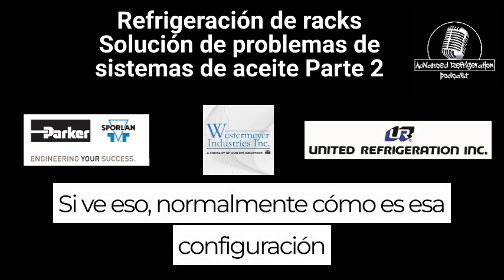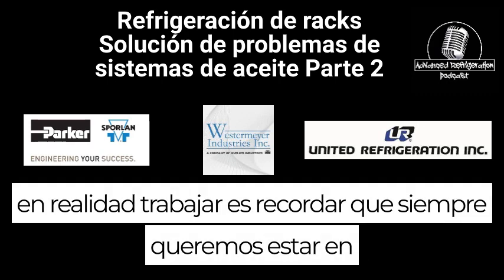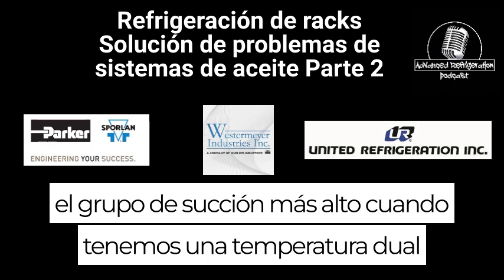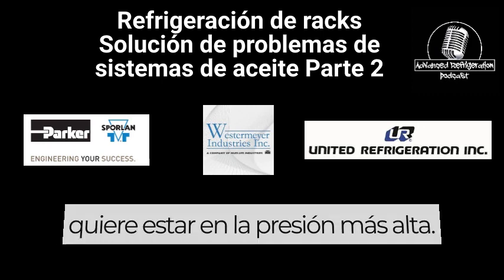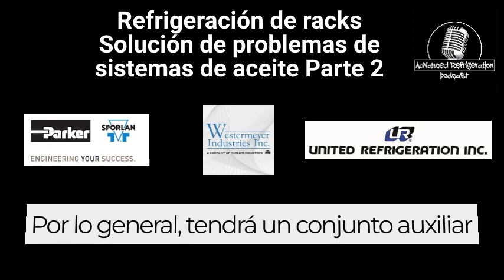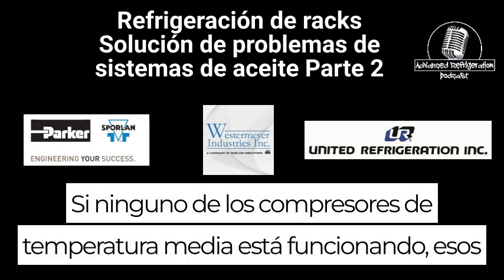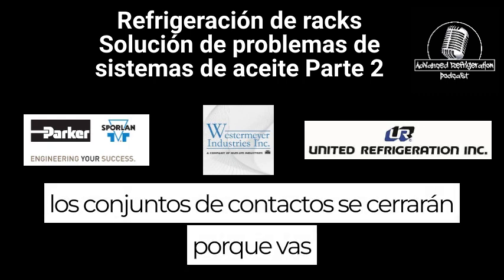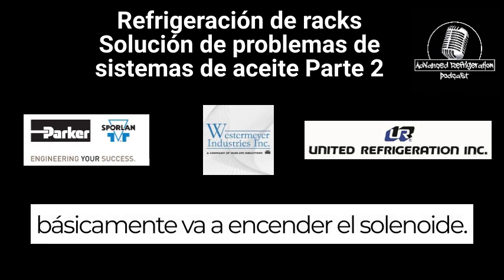If you do see that, typically how that setup is working is, remember, we always want to be at the highest suction group when we have a dual temp header. When we do a dual pressure header, we want to be at the highest pressure. The way that one works with the solenoid is typically you will have an auxiliary set of contacts on your medium temp compressors. If none of the medium temp compressors are running, those contacts will be closed because you're going to wire them up normally closed. And then it's basically going to power up the solenoid.